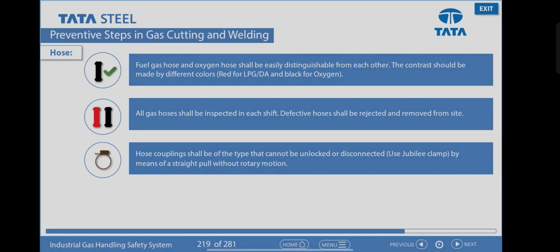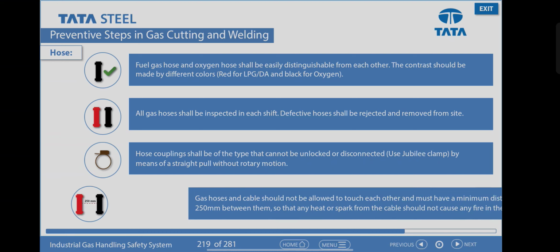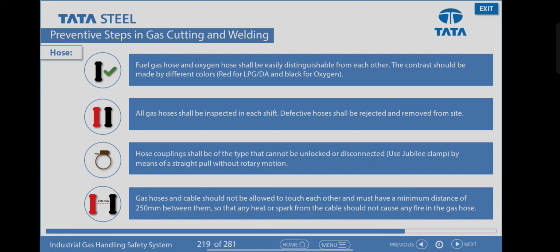Hose couplings shall be of the type that cannot be unlocked or disconnected by means of a straight pull without rotary motion. Gas hoses and cable should not be allowed to touch each other and must have a minimum distance of 250 mm between them, so that any heat or spark from the cable should not cause any fire in the gas hose.